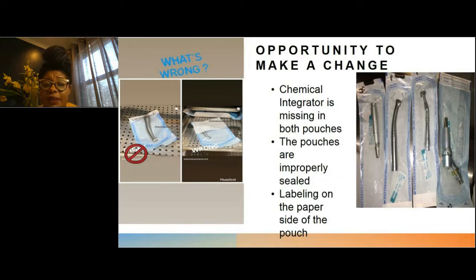So the picture on the left will show you a handpiece that was bagged inside of a pouch that was too small for it, and a pouch that was way too big for it. It's important to know that air acts as a barrier to steam, and you need to make sure that your peel pouches are properly sealed, so that air is not a barrier to that, okay?